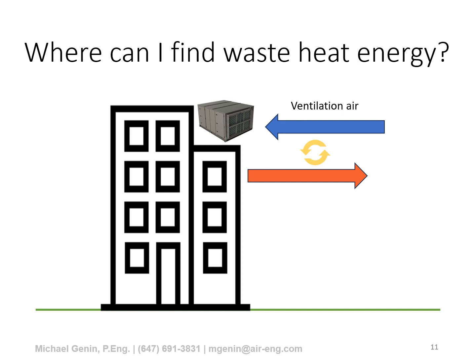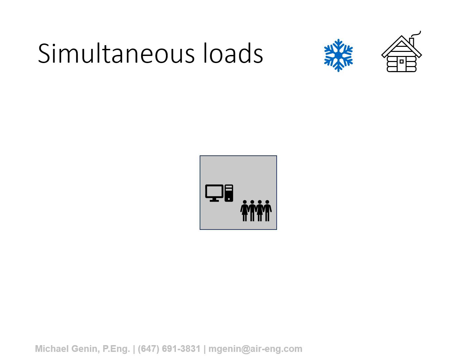So we've discussed heat recovery in the ventilation air, and now we're going to move on to talk about heat recovery internal to the building. To better understand the concept of simultaneous loads and where they may take effect, I want you to think of a very small building or perhaps even a detached house where we have one zone. There might be people and computers and lights inside this building, and they are generating heat. And we're talking from a cold climate point of view here, so it is very cold outside, it's winter time. These devices, or the internal heat load, are not sufficient to heat the space. We have a tremendous amount of heat loss to the outdoors, and so we have to burn some kind of fuel in order to maintain this zone. This zone is in heating mode.